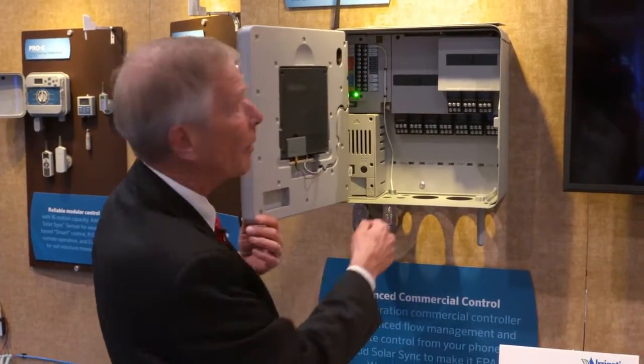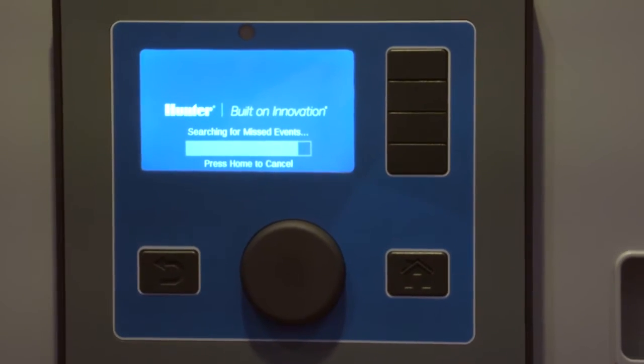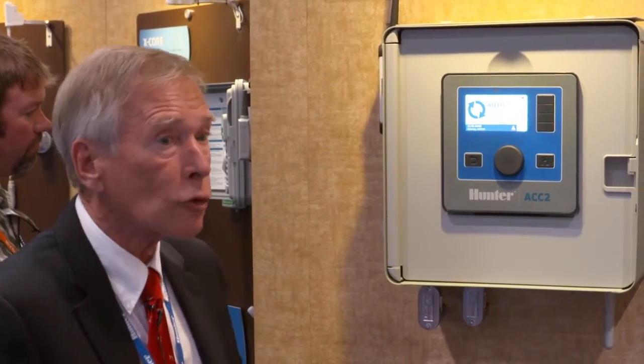Here's another cool thing about power outages. The computer reboots after the outage and replays the events it should have been running. It knows where it should be in real time. It will resume irrigating where it ought to be at this time of day and finish at the end time it was scheduled for. You will miss the smallest amount of irrigation possible after a momentary power outage — it will not just wait for the next start time, but will resume and recover as much irrigation as it possibly can.